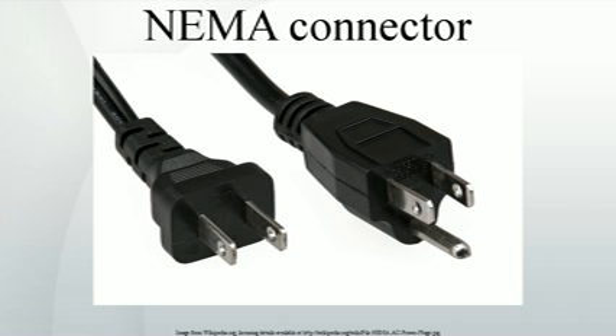NEMA 14. The NEMA 14 devices are 4-wire grounding devices, hot hot neutral ground, available in ratings from 15A to 60A. Of the straight-blade NEMA 14 devices, only the 14-30 and 14-50 are common. The 14-30 is used for electric clothes dryers and the 14-50 for electric cooking ranges. The voltage rating is 250V. They are essentially the replacements for the NEMA 10 connectors above with the addition of a separate grounding connection. All NEMA 14 devices offer two hots, a neutral and a ground, allowing for both 120V and 240V, or 120V and 208V if the supply system is three-phase rather than split-phase.